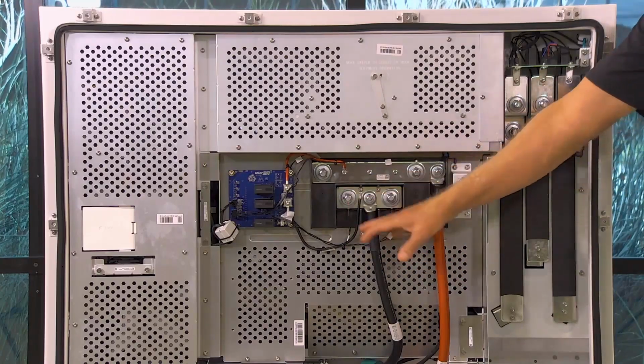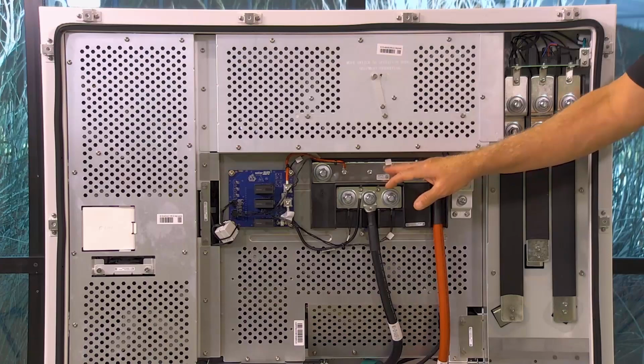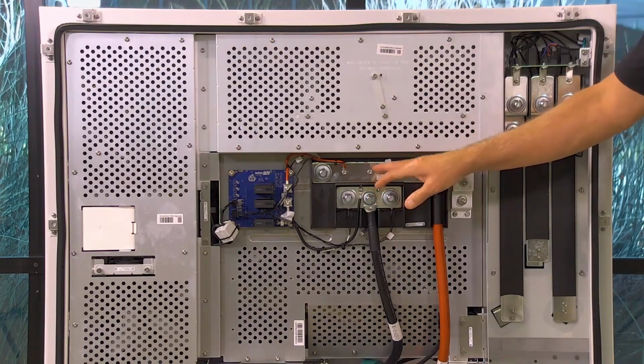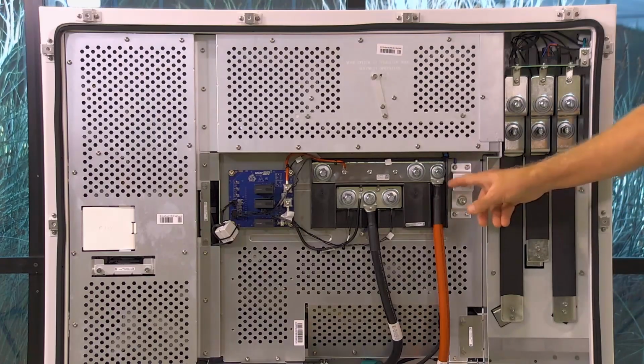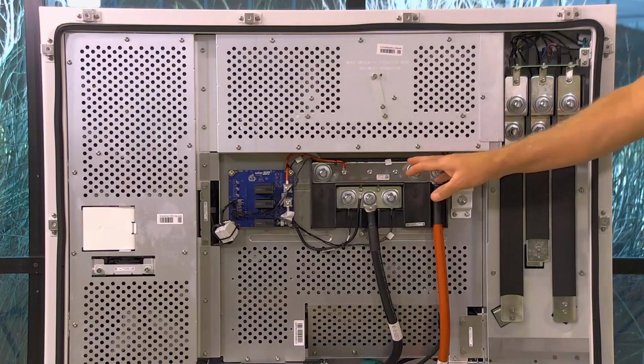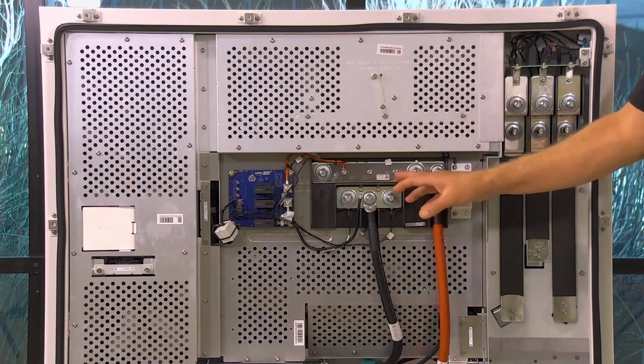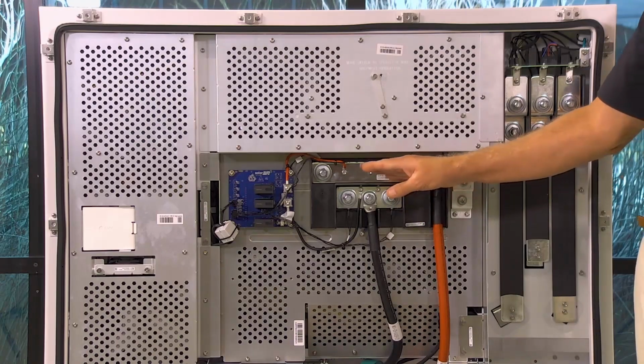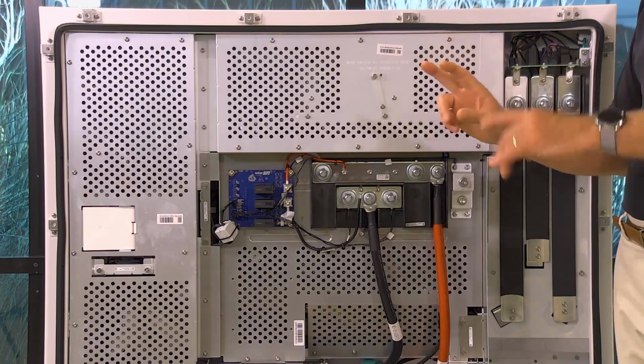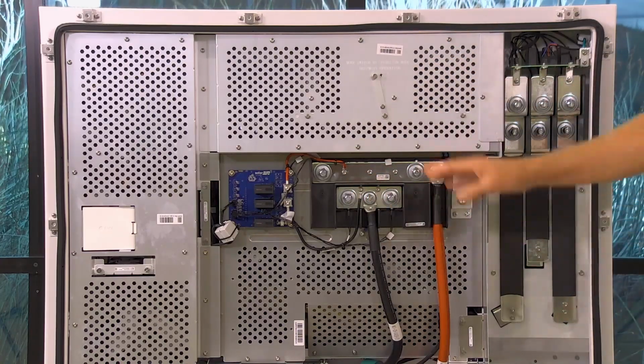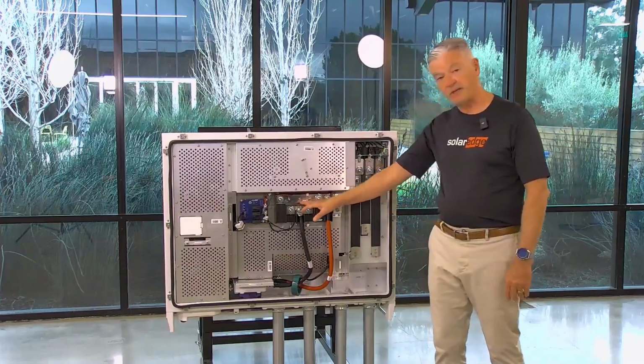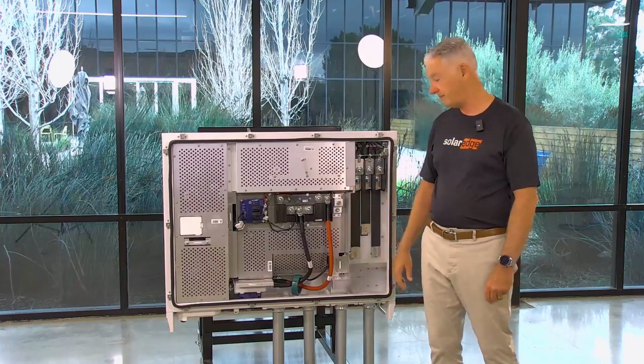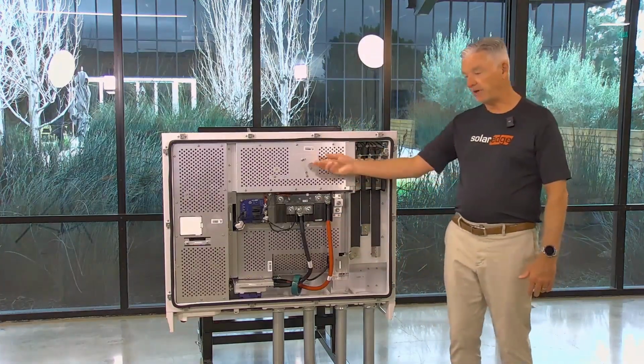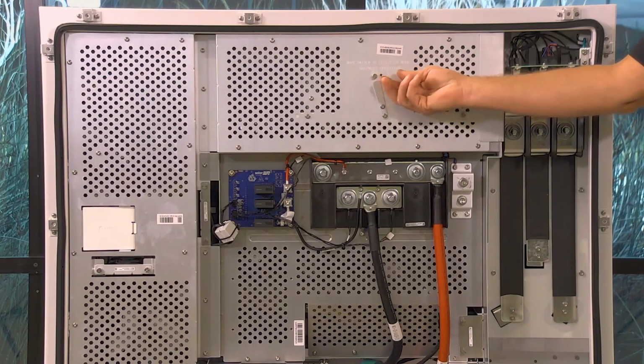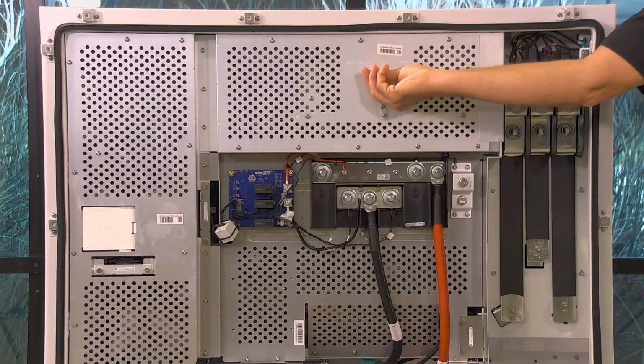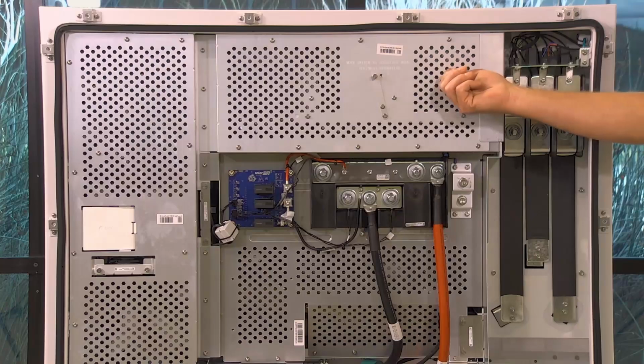In the center portion is the DC terminal block. It too is a dual terminal block, up to 600 kcmil conductor, either copper or aluminum. Here's the ground bus bar for the DC side. You can connect one large combiner with large conductors on the DC terminal block, or you can connect a large combiner with 2 circuits coming out, parallel circuits, on the dual terminal block. Or you could have 2 smaller combiner boxes connected individually to the dual terminal block on the DC side. And lastly, there is the AC contactor lockout switch that has to be removed from its shipping position by unscrewing this screw and moving it over into the operation position.